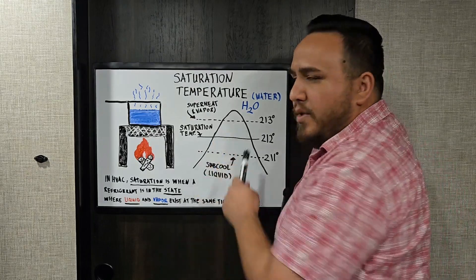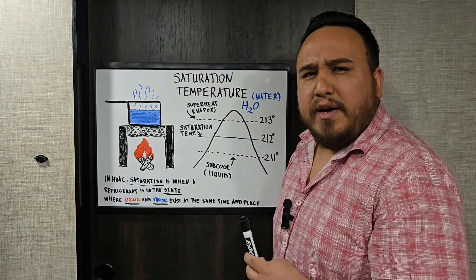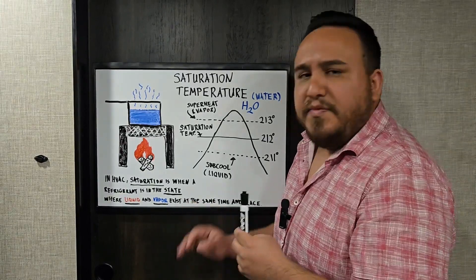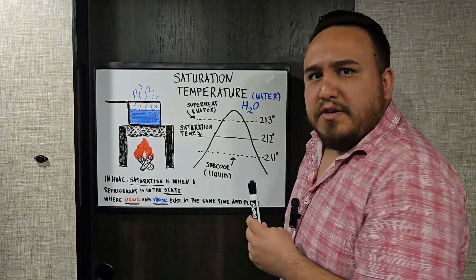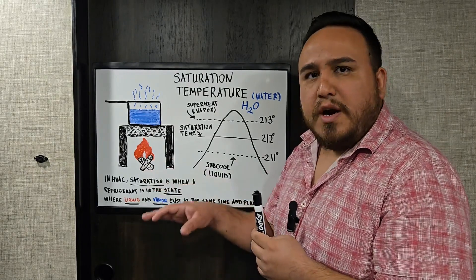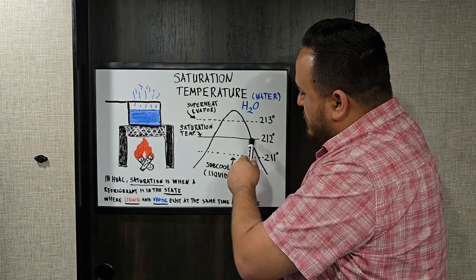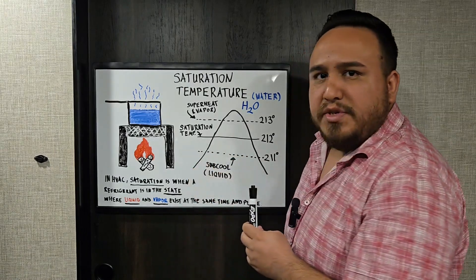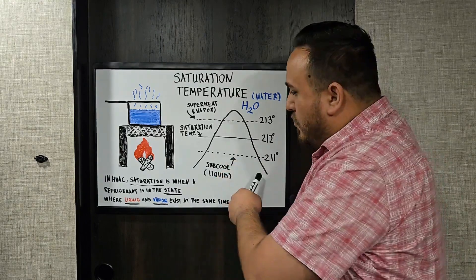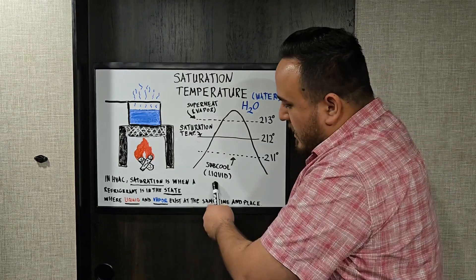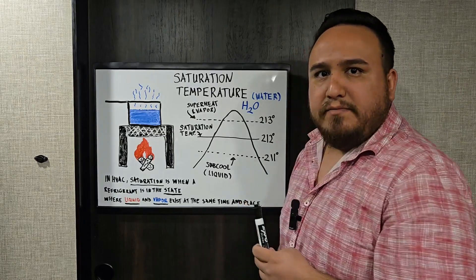That complete vapor state is known as superheat — in another video I'm going to talk about superheat and subcool. For now, let's focus on saturation temperature. As my water is in a state of vapor and starts to reject heat and drop in temperature, it hits 212 degrees again — that saturation temperature — and then decreases further. Once it hits 211 degrees and lower, my water should once again be in a complete state of liquid, or subcooled, meaning no vapor exists beyond that point.